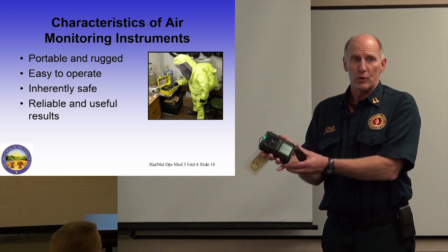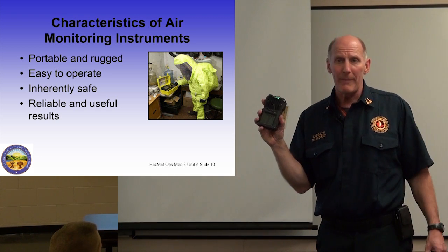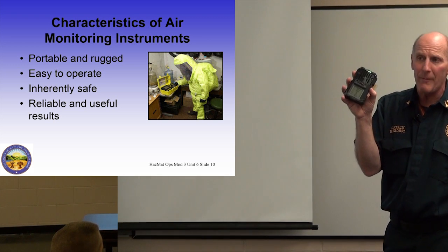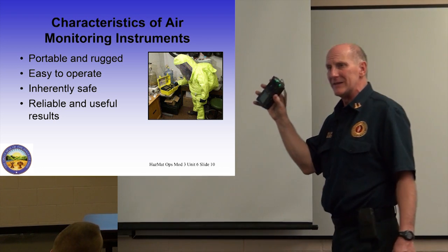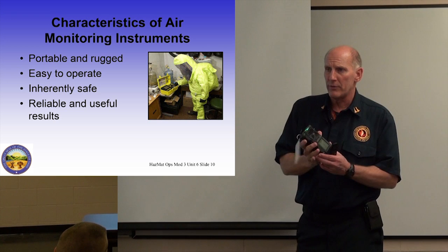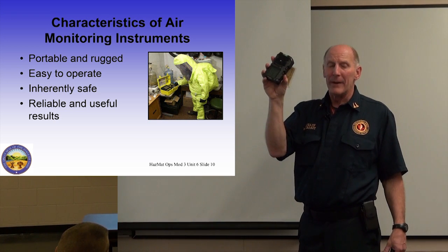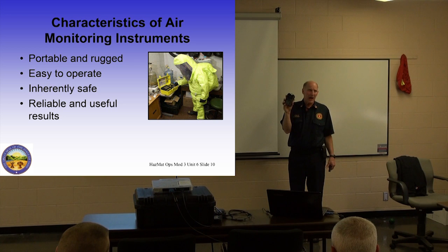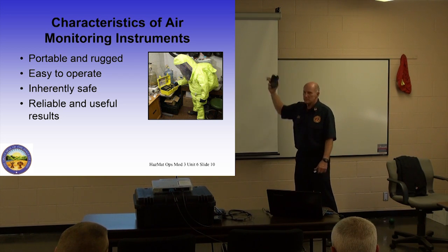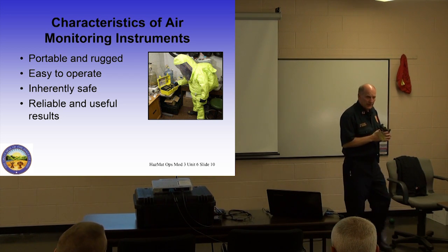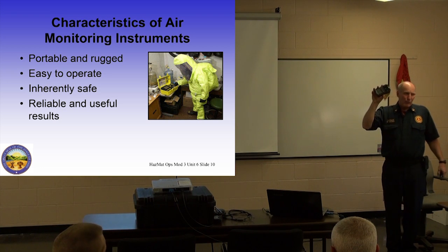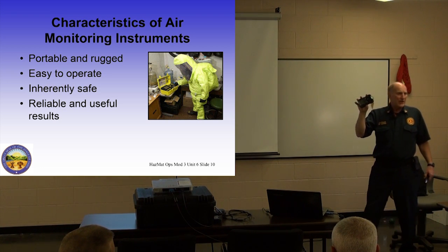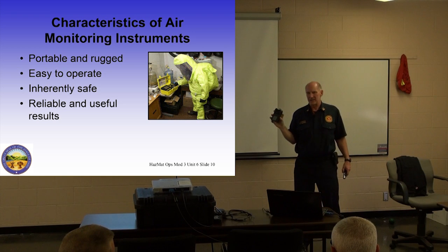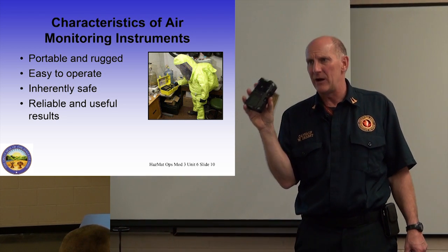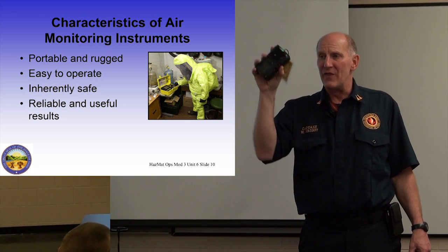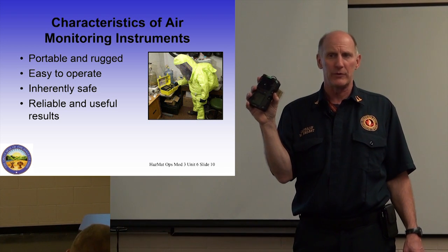We'll talk about turning it on, fresh air calibration, and anything else that needs to be done to this in the second part of this series. But I need to know how to operate it, and it's got to be relatively easy to operate. Inherently safe — I would not want to take something into a potential gas leak that could ignite that gas leak. So they have to be inherently safe. We don't want this to ignite the atmosphere we're working in.